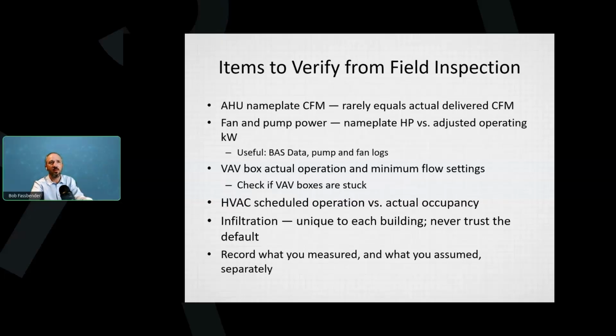Okay, we talked about nameplate versus the actual CFM. I think a lot of this is redundant. Useful information is building automation data, pump and fan logs. I ran a whole study for someone just using some fan logs, actually pump logs. I was able to run an entire study on the building, figure out the loads from just the pumping data and the temperatures.